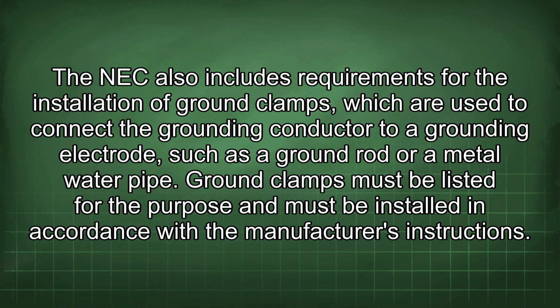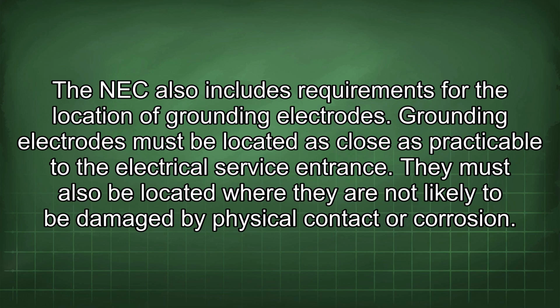Ground clamps must be listed for the purpose and must be installed in accordance with the manufacturer's instructions. The NEC also includes requirements for the location of grounding electrodes. Grounding electrodes must be located as close as practicable to the electrical service entrance. They must also be located where they are not likely to be damaged by physical contact or corrosion.